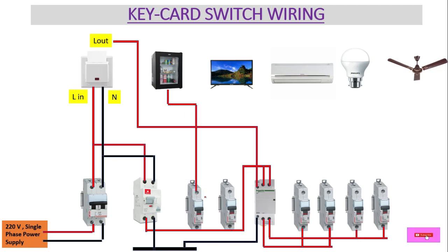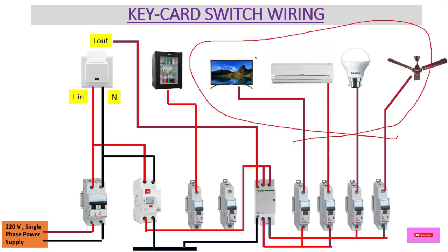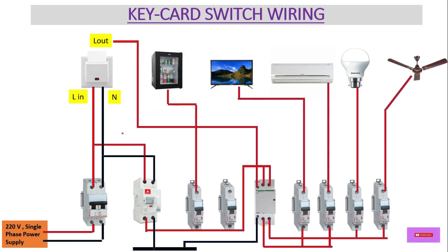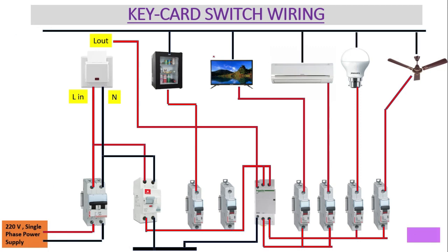From the output of each SP MCB, we can feed power to individual devices like AC, TV, fan, and lights. All these loads are operated through the key card switch, except for the refrigeration item. For the neutral wiring of the loads, neutral connects from the neutral busbar to every load. Up to here we have completed the wiring.